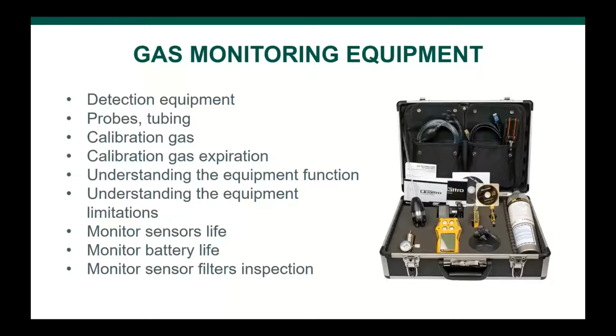Your sensors' life. The sensors on these pieces of equipment have a shelf life. So you need to make sure that during the equipment's self-testing, all the sensors are working properly. Your battery life is very important. Always use a fully charged monitor. And you also have to check the filters that protect those sensors in your equipment. Inspect those and make sure they're in good shape.